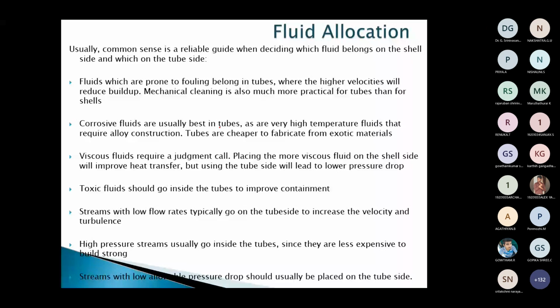And then the next one, high temperature. As I said earlier, if the fluid is very high in temperature, it is better to go for the tube side, not the shell side. Right? If both high pressure and high temperature fluid is available, then it is better to select the tube side, not the shell side. Because if anything occurs during operation, say due to high pressure or temperature the tube explodes, then what will happen? The tubes are surrounded by the shell, so it will not affect the environment. If the outer shell is at high pressure and it explodes, then definitely it has an impact on the environment. So it is better to always choose high pressure, high temperature fluid on the tube side.